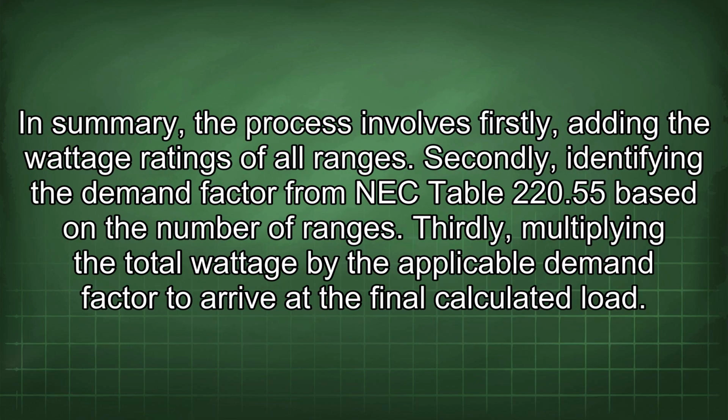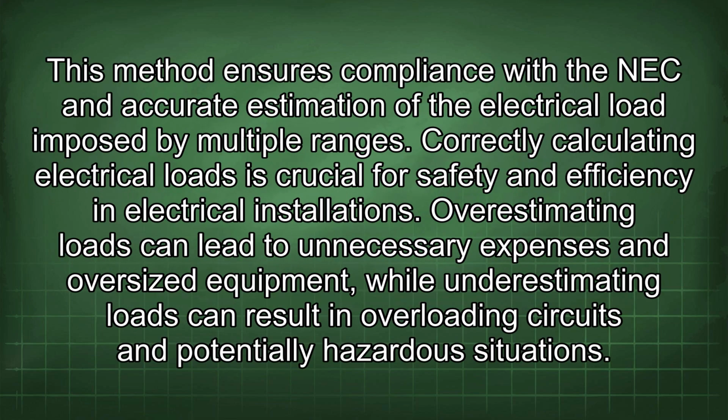In summary, the process involves firstly adding the wattage ratings of all ranges. Secondly, identifying the demand factor from NEC Table 220.55 based on the number of ranges. Thirdly, multiplying the total wattage by the applicable demand factor to arrive at the final calculated load. This method ensures compliance with the NEC and accurate estimation of the electrical load imposed by multiple ranges.